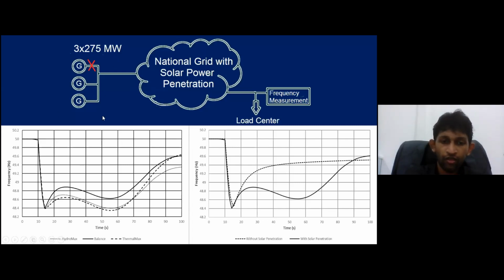This is shown in this figure, and as you can see on the left graph, there is a fluctuation of the frequency. This is due to the solar fluctuation. It hits 48.4. We have installed under frequency load shedding almost all over Sri Lanka. The schemes occur, and then the frequency is restored by governor response action.